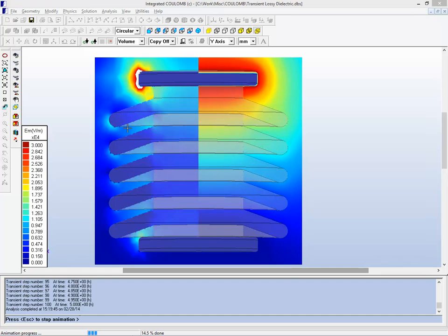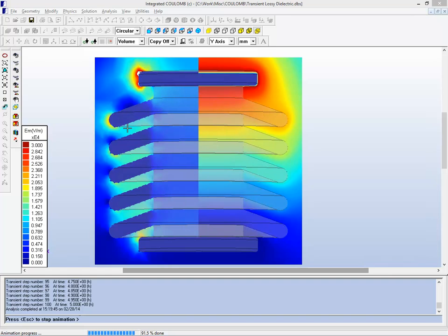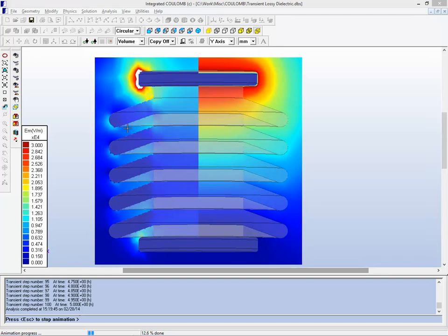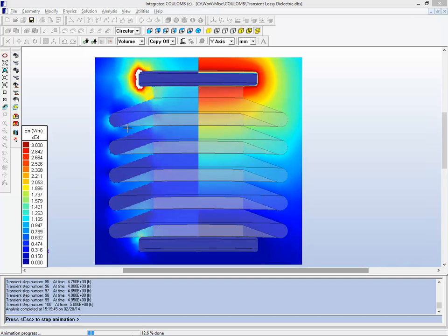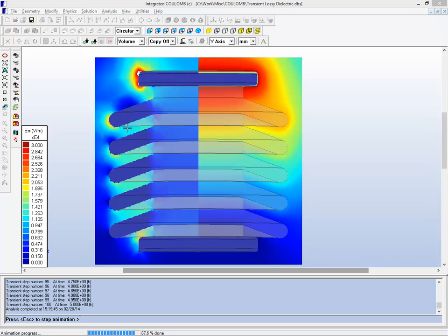years, but eventually it will happen, and it is something that in the work that I do, I have heard many times from people: we have a very good insulator, we flip the switch, turn on the high voltage, and a few months later, the device fails. And when they do the analysis, what they see is that the extremely small conductivities over the course of a long time, depending on the values, lead to a very different field distribution than what they had over the shorter terms.